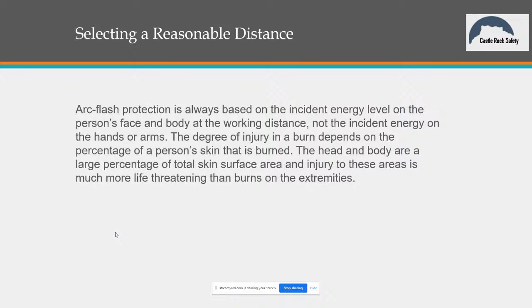What's the level of incident energy that requires us to use a face shield when we're on the utilization side? When working on your side, where do I have to start putting that face shield on? Is it 50 volts or more? No, what incident energy? Incident energy, 1.2 calories. Right? Okay.